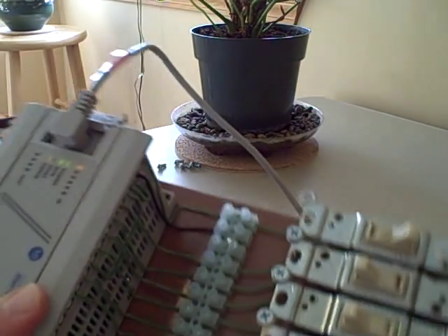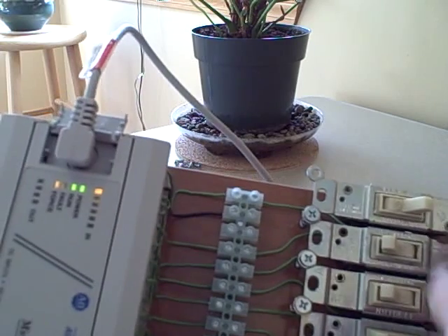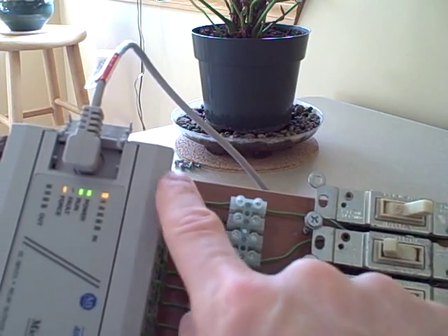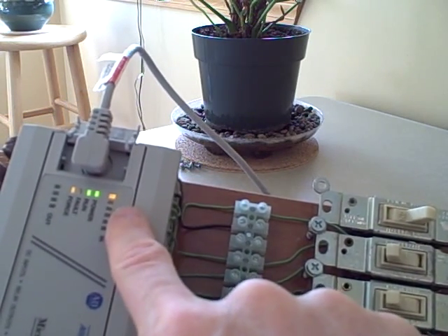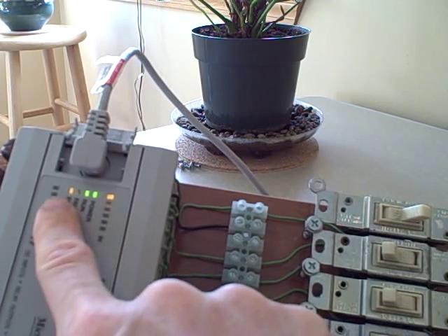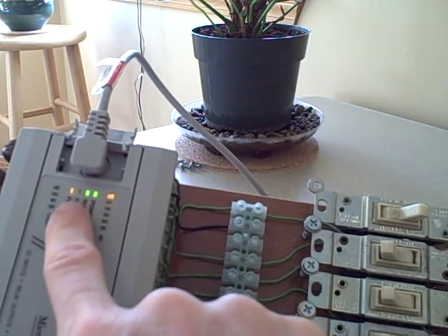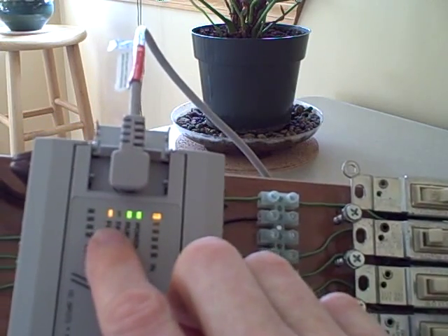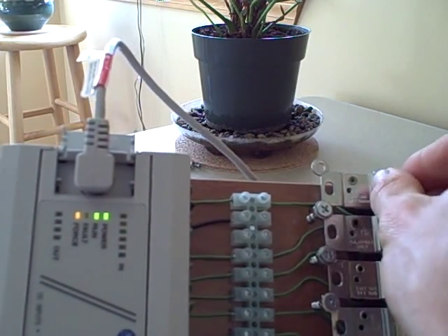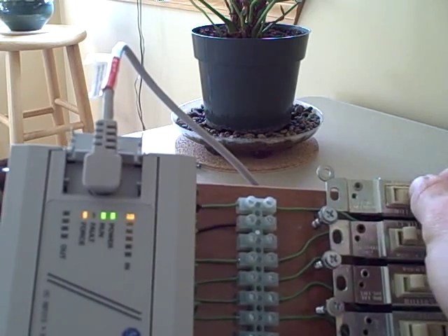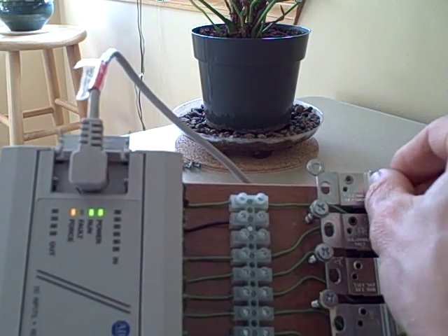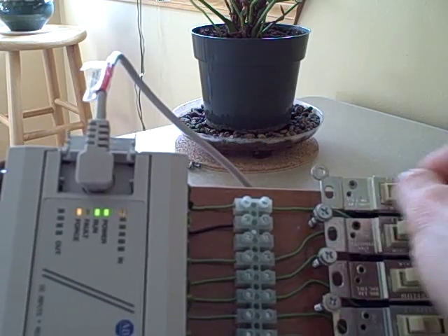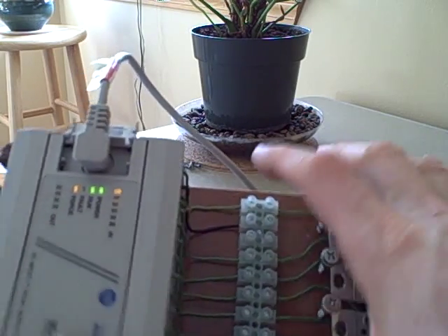And if we pan over to our PLC, we see some interesting things here. We see my input switch on. I'm still energized on input bit 0. I am no longer energized on output bit 0, and I have a new light on my display, a light on the PLC that says force. If I turn the switch on and off, you'll notice the output bit does absolutely nothing. It has been forced to a 0 state, no matter what the input does.